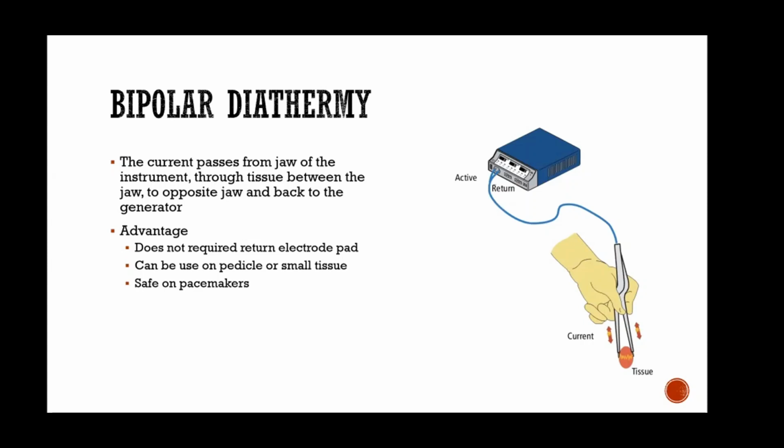For example, you can use bipolar diathermy for circumcision. Don't use monopolar diathermy during circumcision. Also, bipolar diathermy is very safe if the patient has a pacemaker.